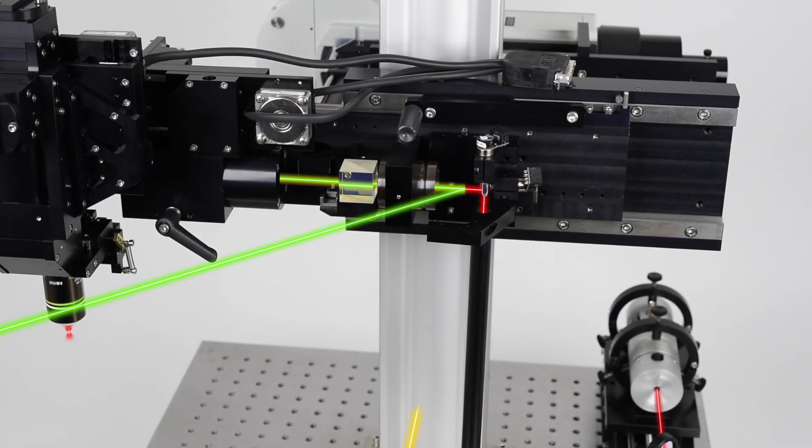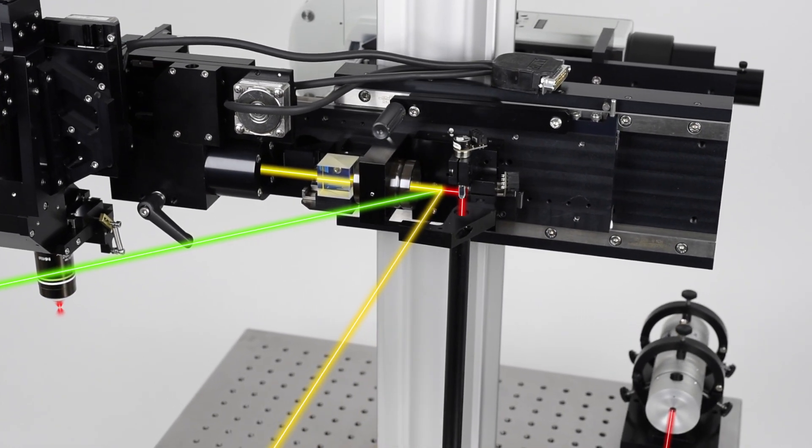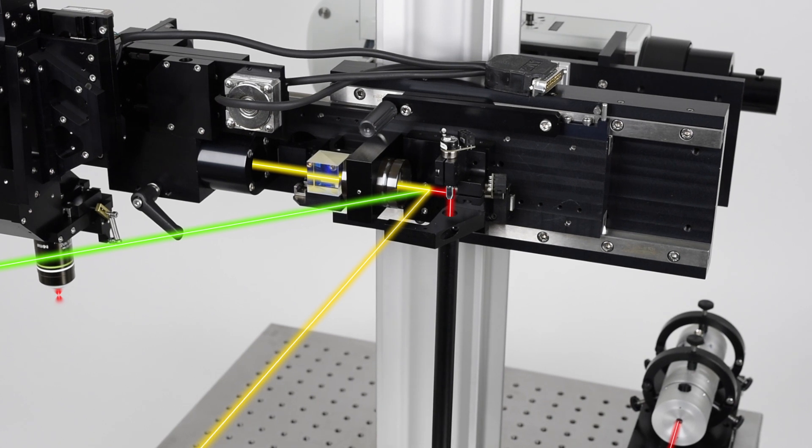Finally, two additional laser beams can be added to the system between the actual scanners and scan lens via a scan lens dichroic input. There is an engineered location to accept dichroic mirrors to couple one or two more light sources into the scan lens.